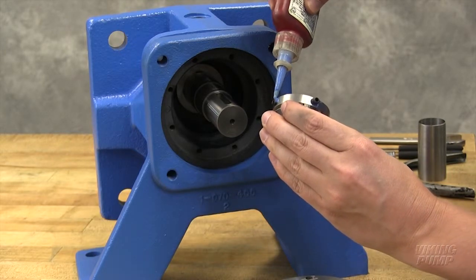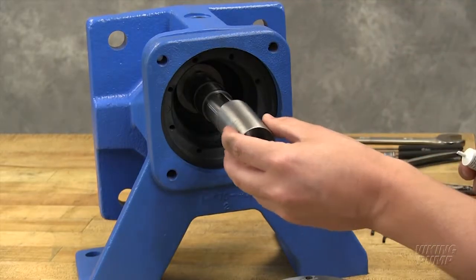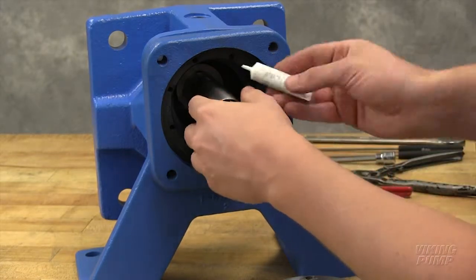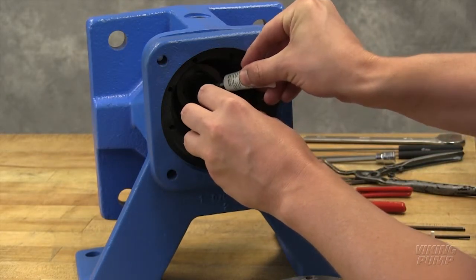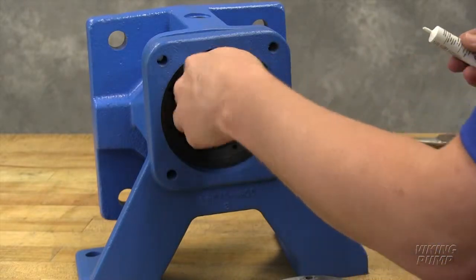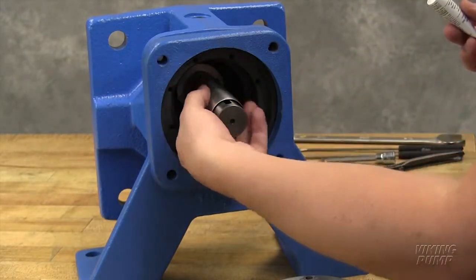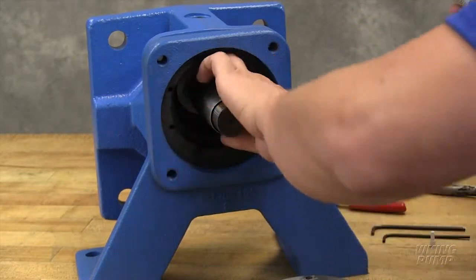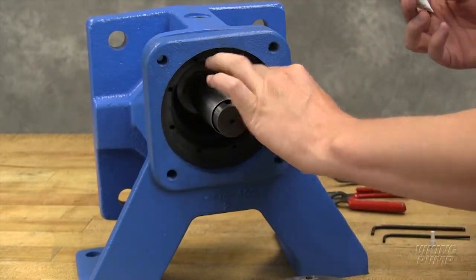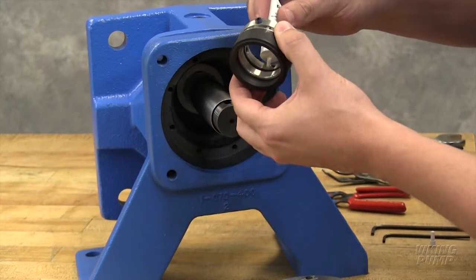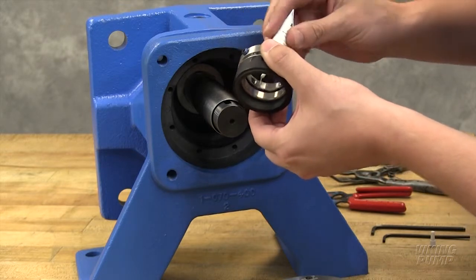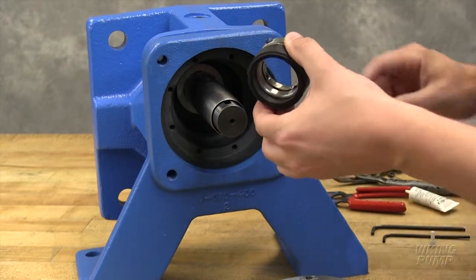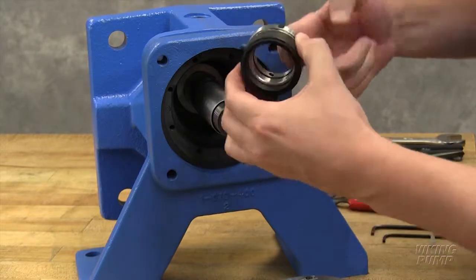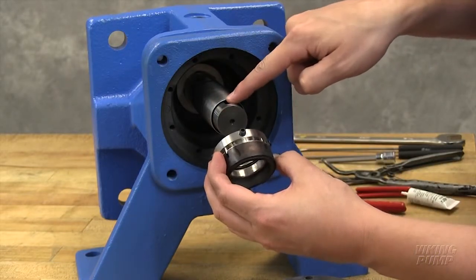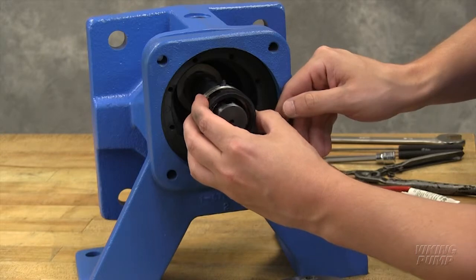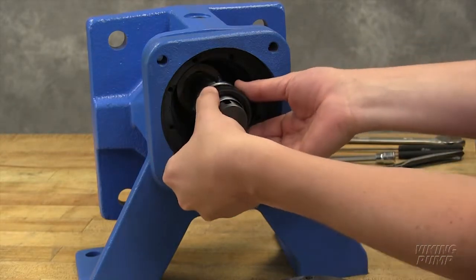Coat the drive shaft, tapered installation sleeve, and inner diameter of the mechanical seal with a light oil before assembly. Slide the rotating part of the mechanical seal over the installation sleeve on the shaft until it contacts the seal shim. The longer dog point set screw needs to be lined up with the recess in the shaft that is in line with the keyway. This will also align two set screws with flats on the side of the shaft to prevent the mechanical seal from spinning on the shaft.